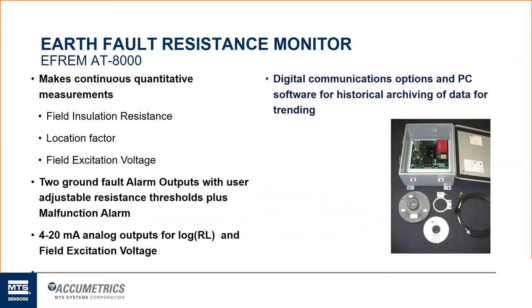We offer two ground fault alarm outputs, which are user adjustable. Those come set from our facility at 100 K ohms and 2 K ohms. So we kind of view that as a warning alarm and then a ground fault alarm. So once the resistance drops below that threshold of 100 K, we will send an initial warning alarm to let the user know, you don't have a ground fault yet. However, you are trending in that direction. Time to start paying a closer look at your machine and schedule an outage so you can investigate further and get that damage repaired if needed.